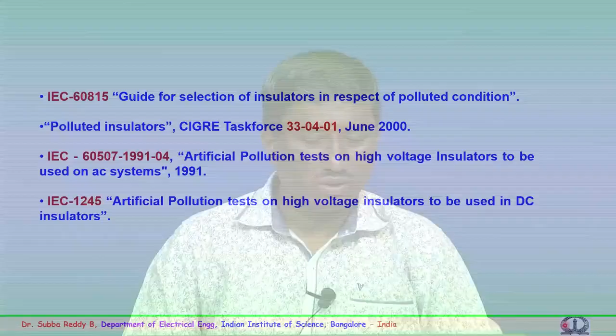I would like to share some information which is in the standards. We have IEC standard 60815. This is a very important guideline which gives information on the selection of insulators, particularly in respect of polluted conditions. It gives the idea of how the creepage length has to be chosen, and how the insulator dimensions have to be chosen depending upon the area where the insulators are being used. There is also a task force by CIGRE 33.04 which has come up with an important document on polluted insulators, giving information on how to use insulators, whether ceramic, glass or porcelain, in various conditions.